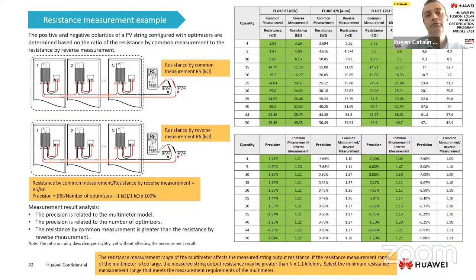We already discussed how to check the string before installing the string with full optimizers. I need to add here that the inverter uses the AC power in order to unlock the optimizer. So this is very important to check before connecting the string with optimizers to the inverter, because if the string is installed correctly, the inverter will automatically start to search for and unlock the optimizers using the AC power.